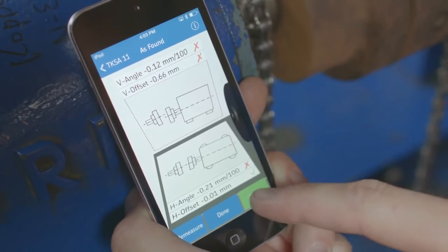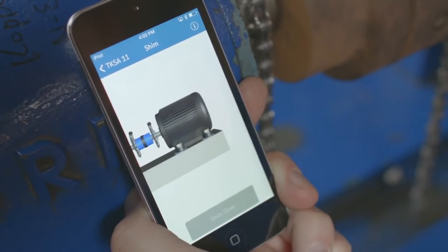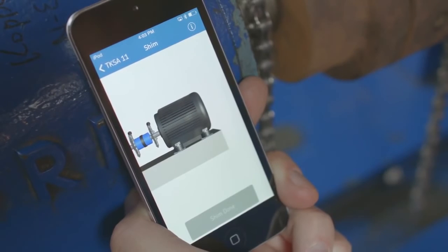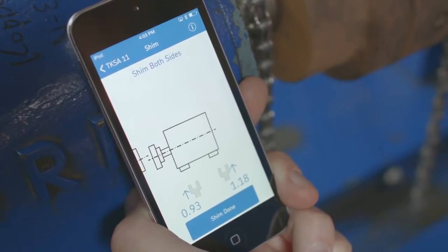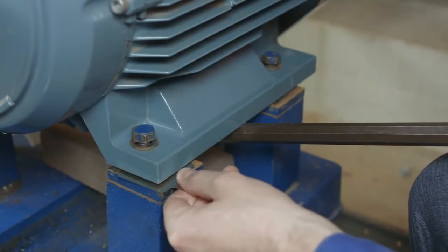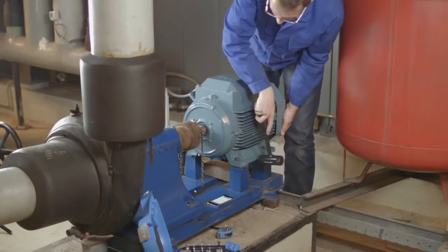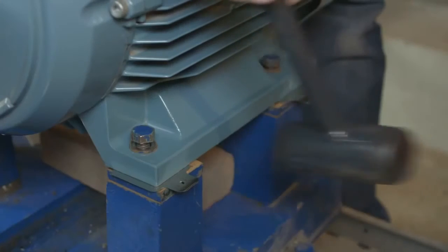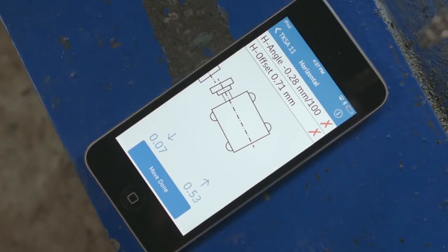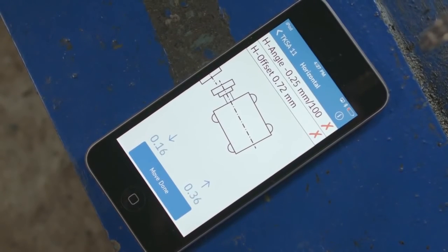After determining the current shaft misalignment, the app guides you through the alignment process. First, by showing what shims are needed for the vertical alignment, and then which movements need to be performed for horizontal alignment. The live view helps you quickly achieve accurate positioning.